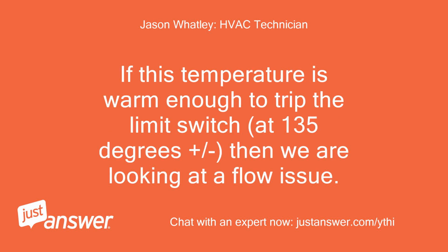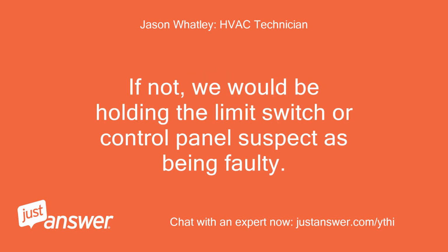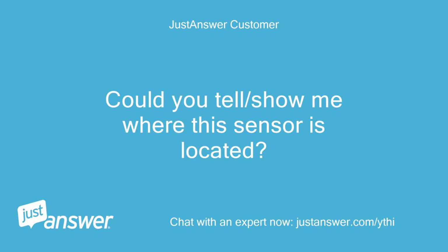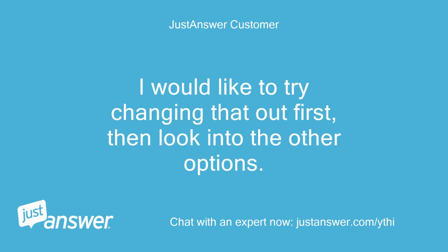The first thing I would suggest is taking the water temperature as it leaves the heater heading to the pool. If this temperature is warm enough to trip the limit switch, at 135 degrees plus, then we are looking at a flow issue. If not, we would be holding the limit switch or control panel suspect as being faulty. Could you show me where this sensor is located? I would like to try changing that out first, then look into the other options.